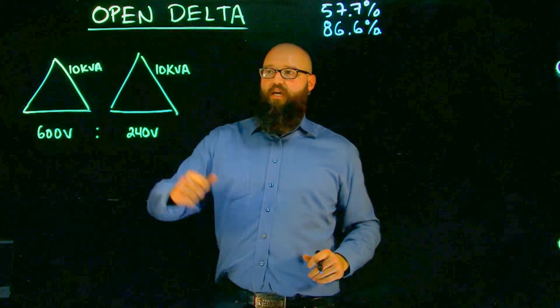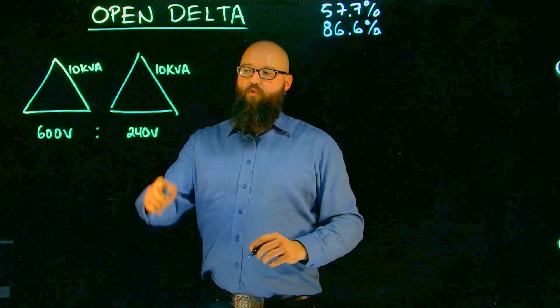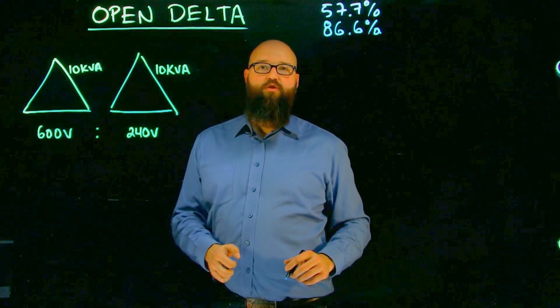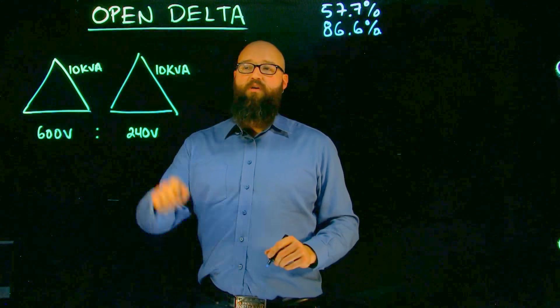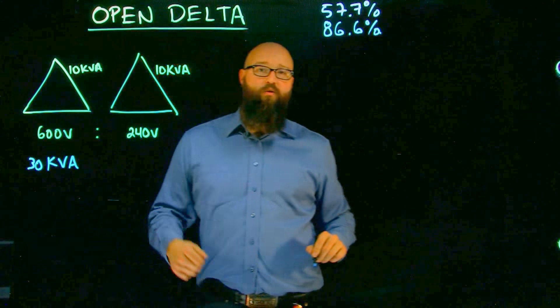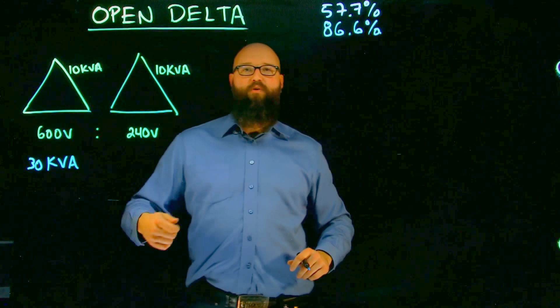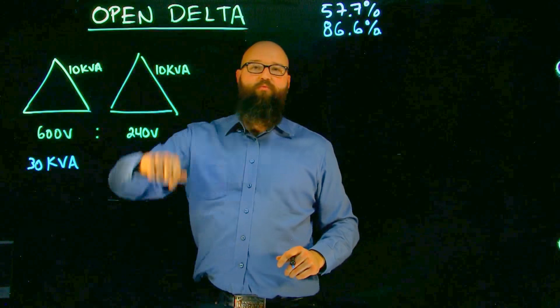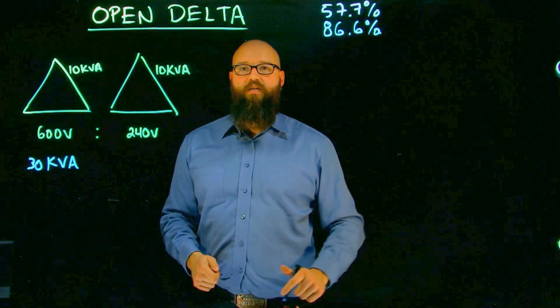So first of all let's look at the secondary. We know that we have a 240 volt, this is a 600 step down to 240 volt delta system. It's a 30 kVA transformer which means it has 30 kVA of output, rated output when all three of our phases or our transformers are connected.